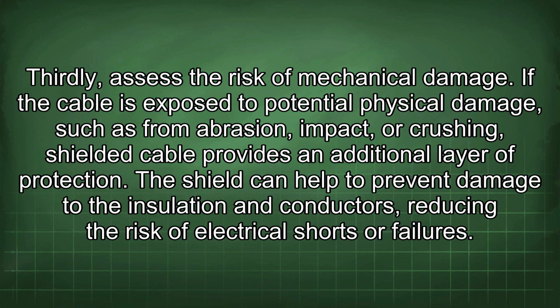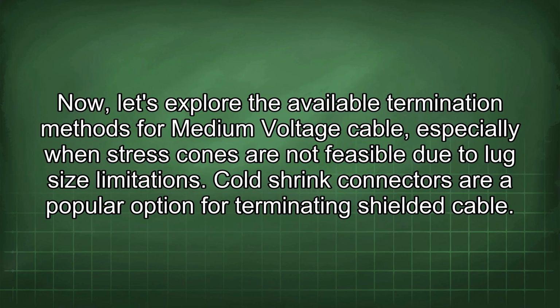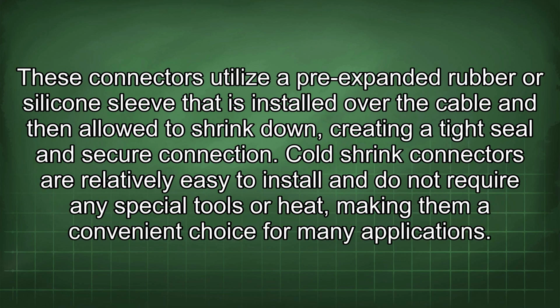electrical shorts or failures. Now, let's explore the available termination methods for medium voltage cable, especially when stress cones are not feasible due to lug size limitations. Cold shrink connectors are a popular option for terminating shielded cable. These connectors utilize a pre-expanded rubber or silicone sleeve that is installed over the cable and then allowed to shrink down, creating a tight seal and secure connection. Cold shrink connectors are relatively easy to install and do not require any special tools or heat, making them a convenient choice for many applications.